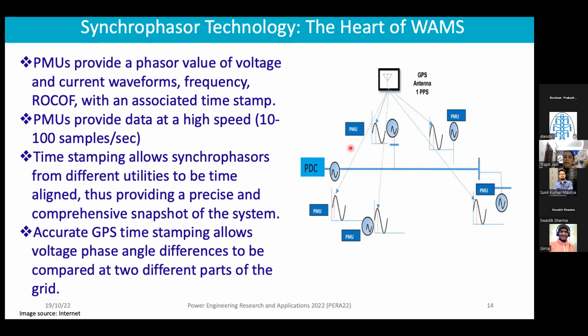PMUs provide phasor values of voltage and current waveforms, frequency, and rate of change of frequency, with an associated timestamp. The main thing is that in SCADA we were not getting these phasor values - we were simply getting the magnitudes of voltage and currents. But here we get these phasor values, which simplifies many things. So the main measurements provided by phasor measurement units are phasor values of voltage and current waveforms, frequency, and rate of change of frequency (ROCOF).